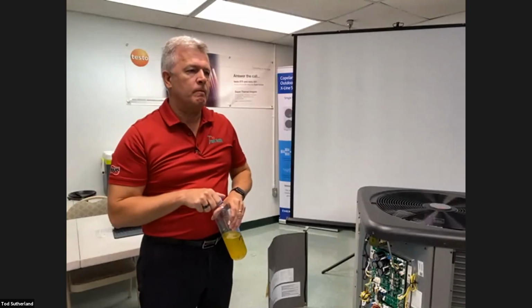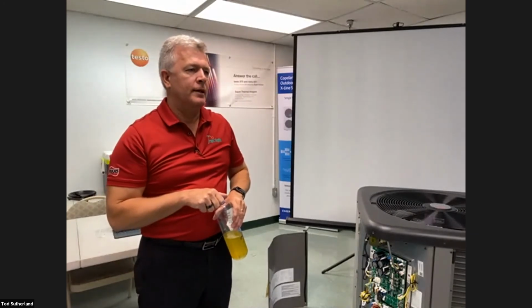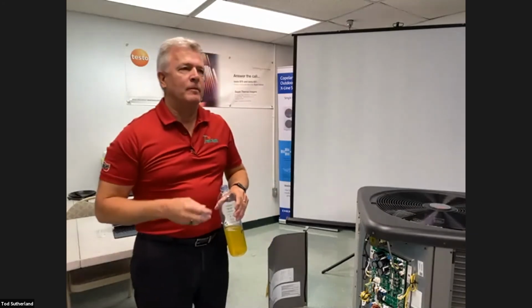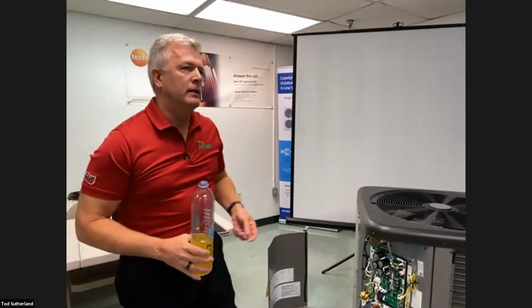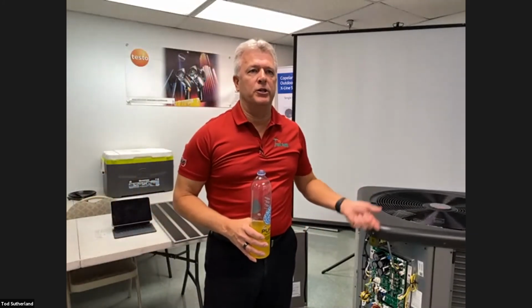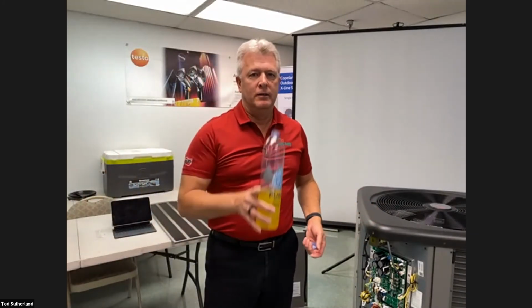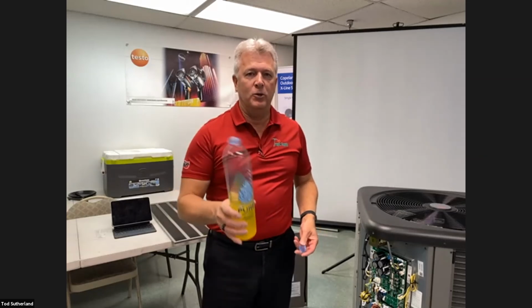John says he's 2 for 2 on that error. Okay. But John, last time, remember you ended up replacing the thermistor, the pressure transducer, and the board, right? And you're supposed to test all three so we know which it is.